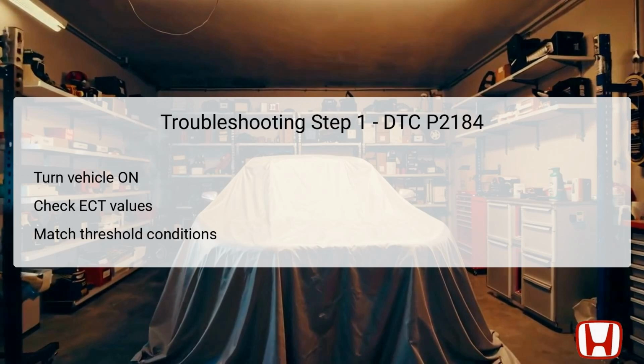If the parameters match the threshold conditions you've identified, it confirms that the failure is legitimate, and you should proceed to the subsequent troubleshooting step. However, if the voltage readings are satisfactory at this moment, it may indicate an intermittent issue. In such cases, close attention to wiring and connections is necessary, as dust or moisture ingress could disturb the readings sporadically.